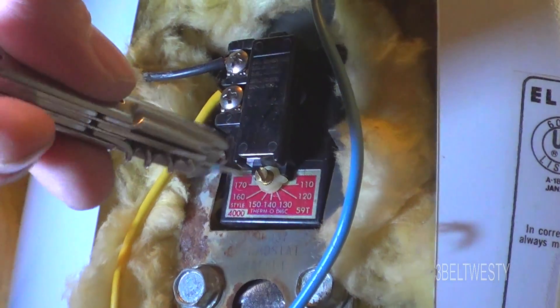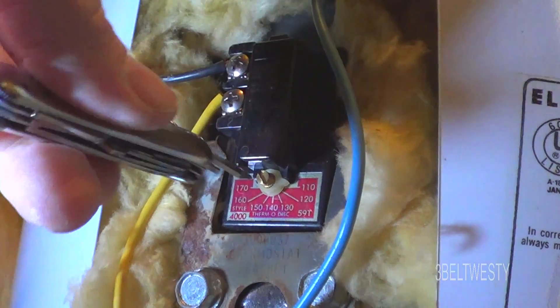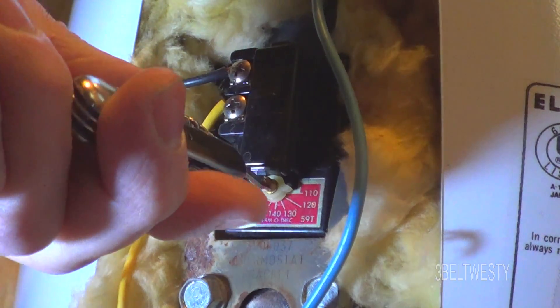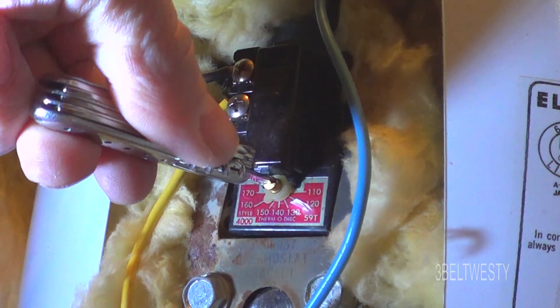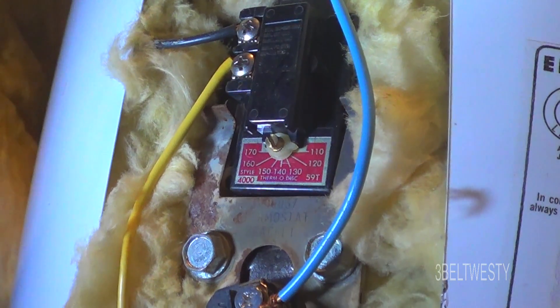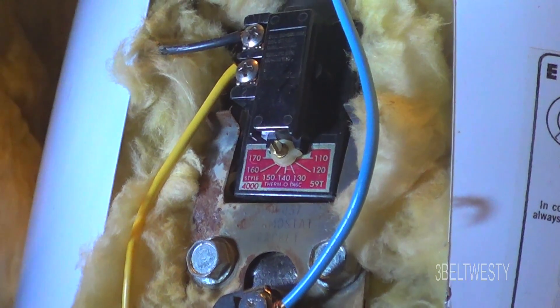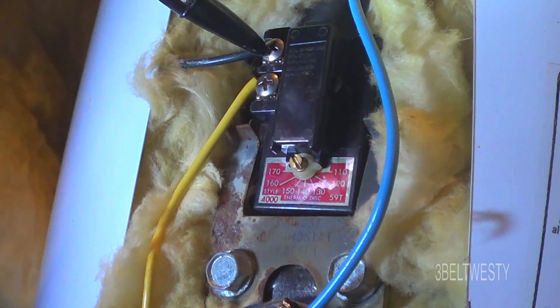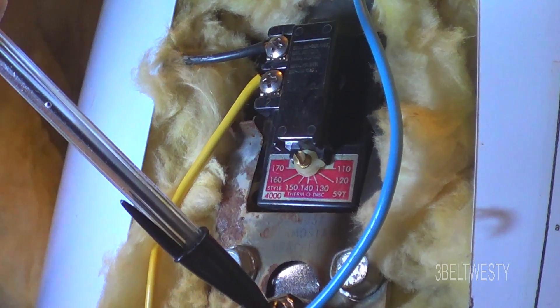Here's a lower thermostat with the problem. I can go through here and set the temperature from 110 all the way up to 170 and it never kicks on, and it's got power here to the black terminal and the blue terminal.